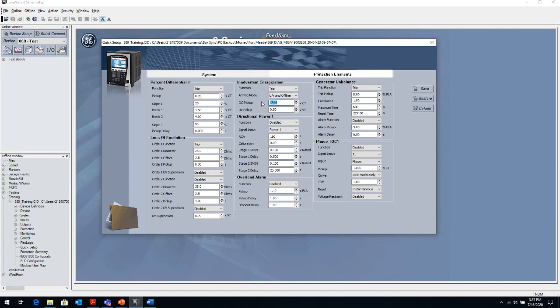The overcurrent, remember that 50 element, the pickup of that, and then the undervoltage element. And then the arming mode, where the undervoltage and offline. Offline is basically if we're monitoring the generator breaker, when the breaker opens up, that's basically the generator going offline. So we can monitor the voltage and the breaker, and either one of those we can go into this protection, or if both. I should expect to see both when the generator is offline. I should expect to see the breaker open and the voltage bus de-energized, the generator bus de-energized.